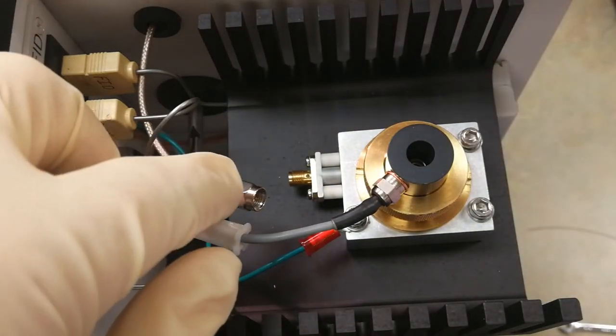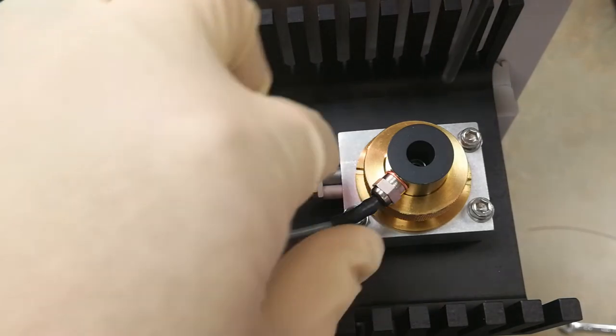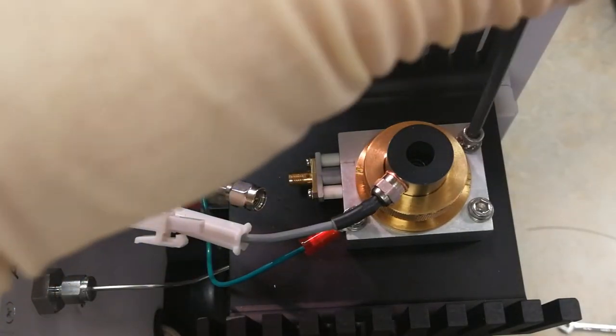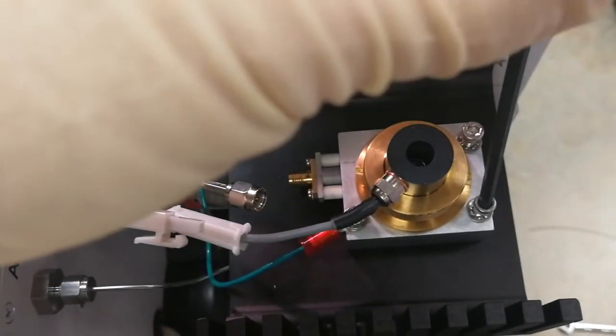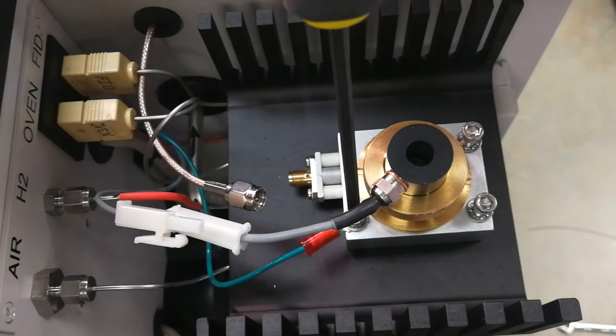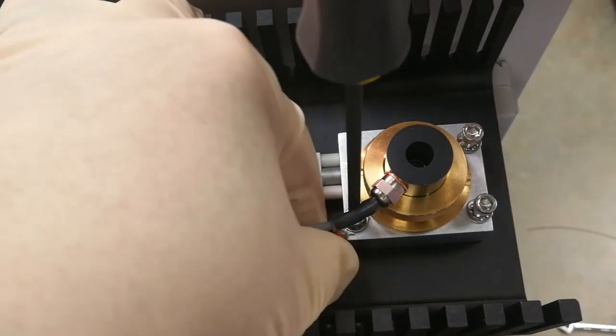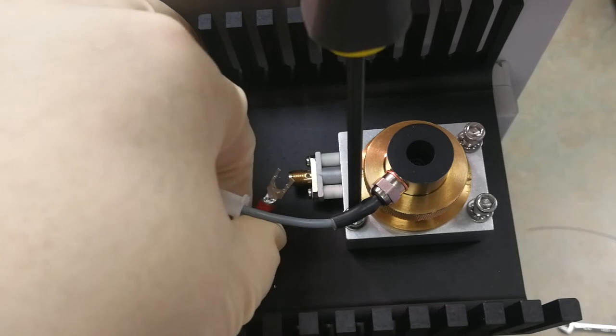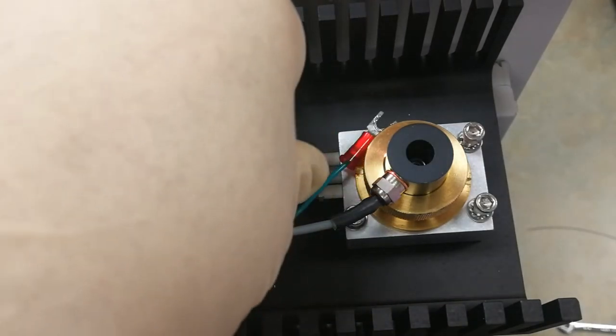Take your 9/64 socket wrench and loosen the three FID block screws. You can take your ground wire loose and just let it hang.